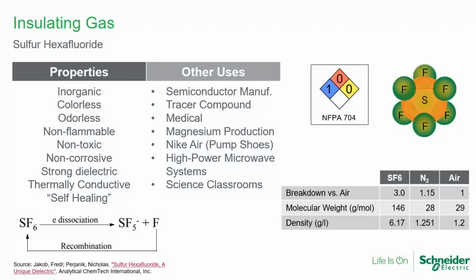And it's important, I think, to know that most of that escapage happens because of SF6 gas handling on site. Either you have to install the switchgear and then fill it with SF6 gas, or you have to remove the gas at some point for maintenance procedures.